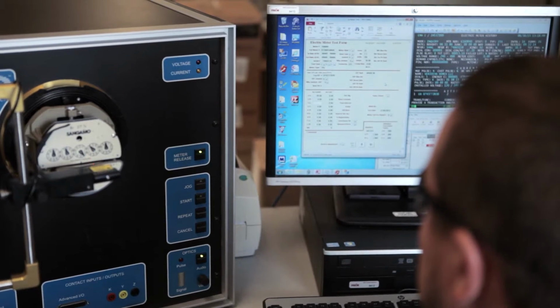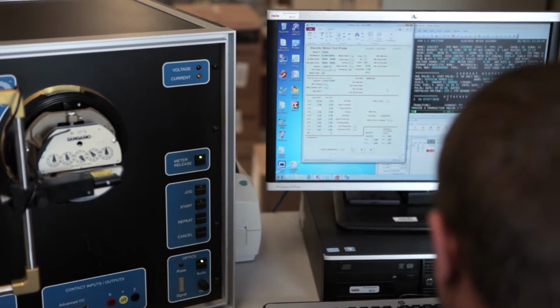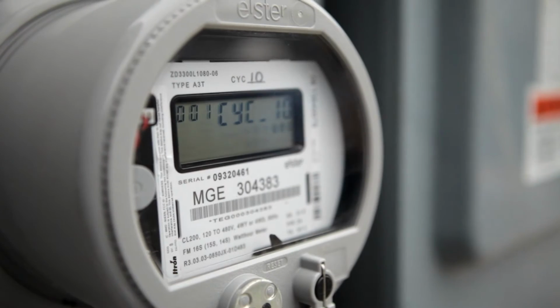The first thing to consider is the rate schedule, which defines what data is required to properly bill that customer. The second is the type of service—is it single-phase or three-phase? And then you have the service voltage. All those items are needed to make sure we get the proper meter in place for that customer.